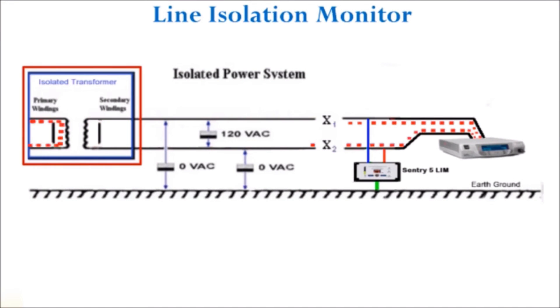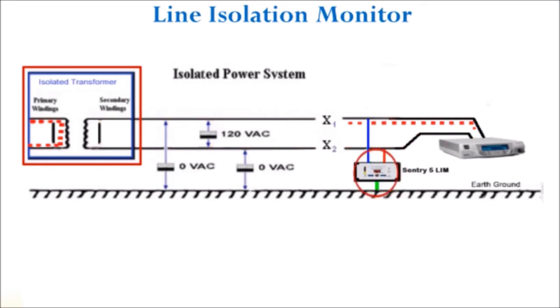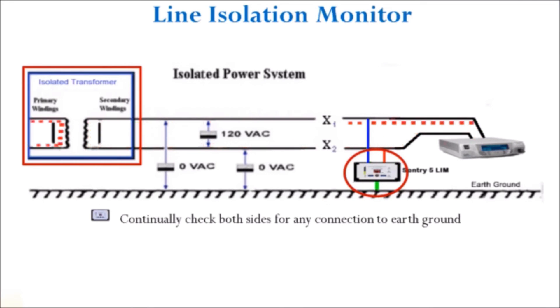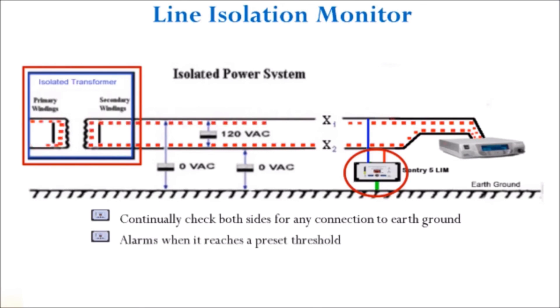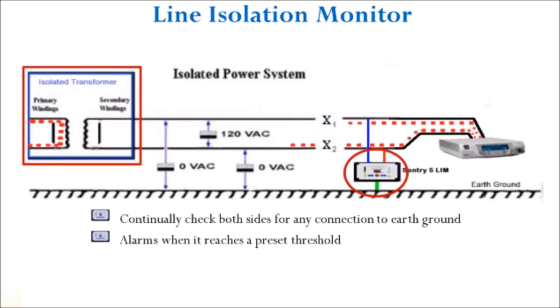In this diagram, you can see that the Sentry 5 is attached to both X1 and X2 so that it is continually checking both sides for any connection to earth ground. And if it should sense some leakage starting to creep in, it will alarm when it reaches a preset threshold. The Sentry 5 also has a built-in test circuit to exercise the alarm without adding to any leakage to earth ground.